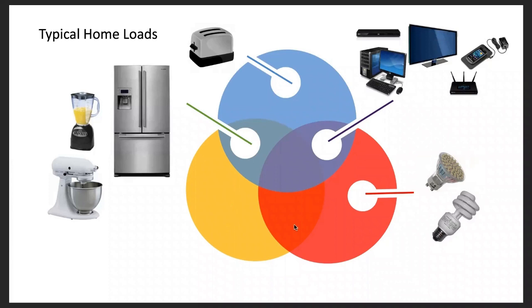Other types of loads that would have inrush characteristics, as shown in this yellow circle, motor loads, for example, or anything that would have a combination of the continuous as well as inrush characteristics, like a refrigerator that would hum along at a certain power level and then surge when the compressor kicks on. That would be sort of in the middle here. And that surge rating is really the peak that you're looking to plan your backup loads panel for. And it is very important when it comes to system planning, that backup loads panel planning, so that you reduce your service calls and make sure that your customers are always happy.